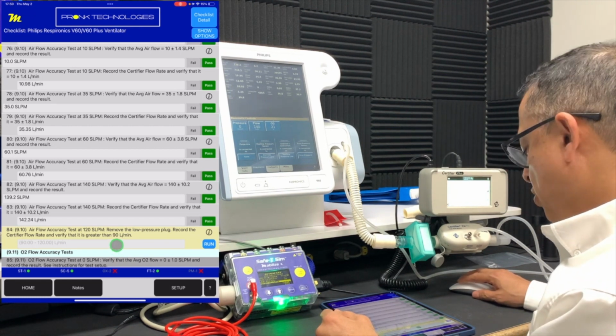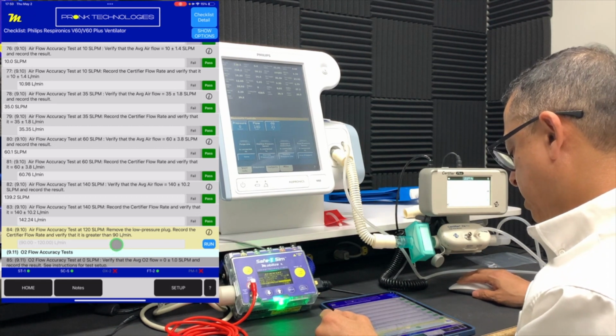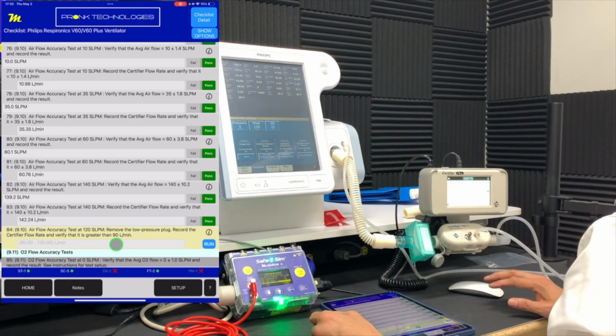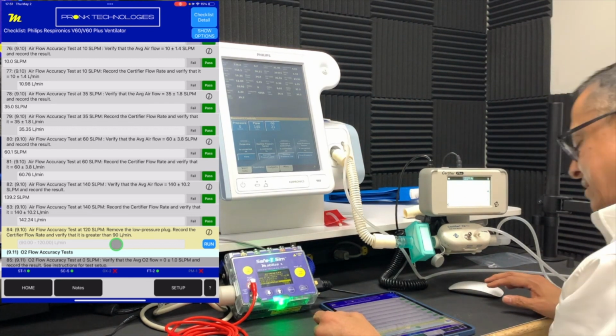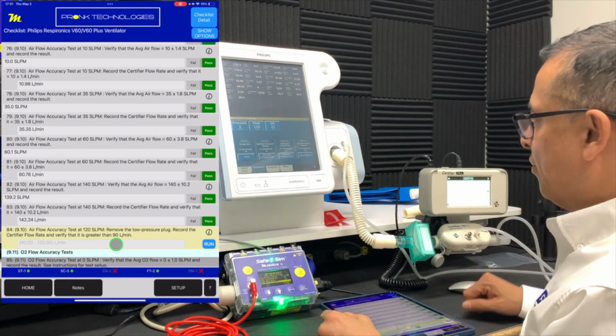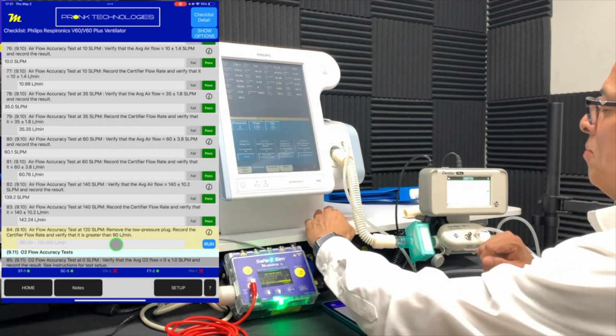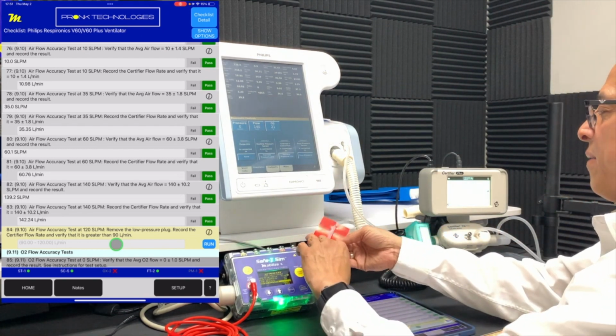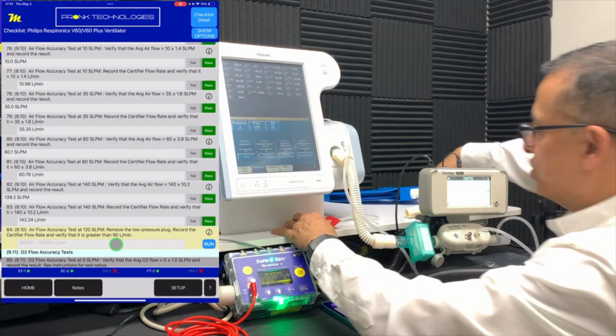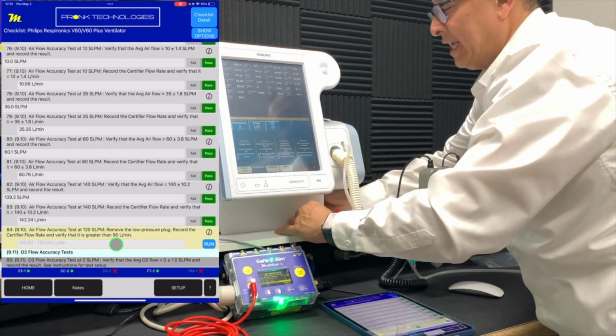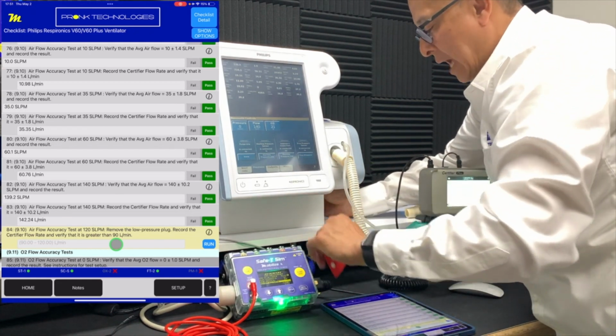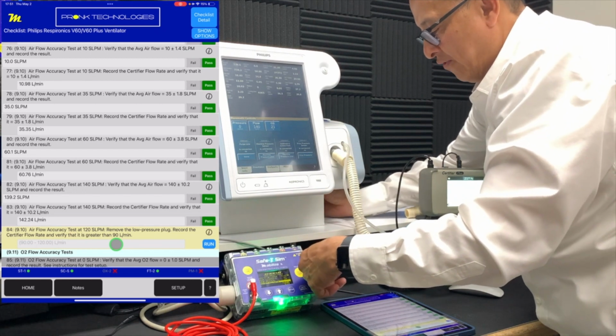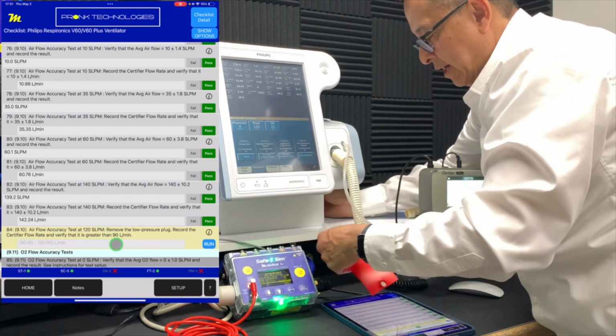Now we want to remove the low pressure plug. And then record what that value is. So now we want to remove this pressure plug from the bottom of the unit, and we'll see that the flow just dropped slightly, but it shouldn't drop out of specification. So we'll go ahead and remove that. Bear with me 1 second while I do that.